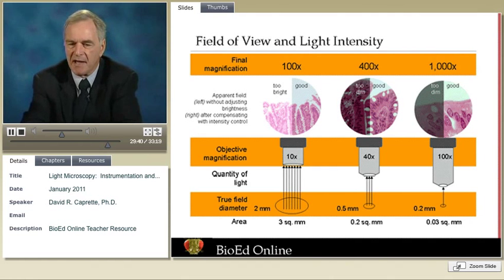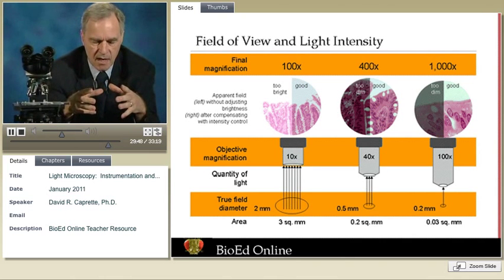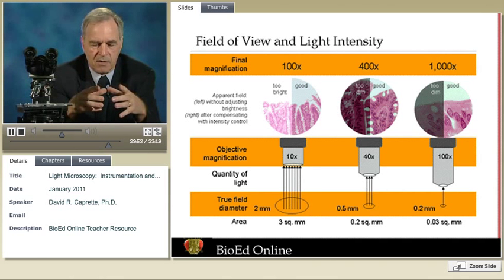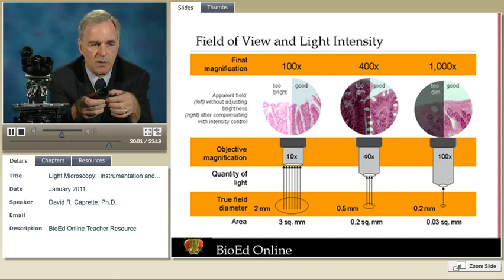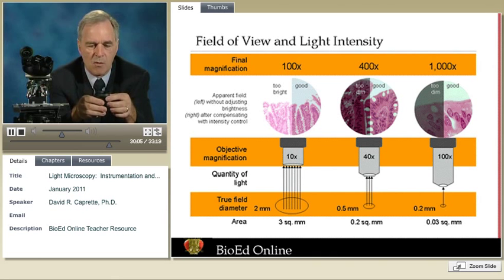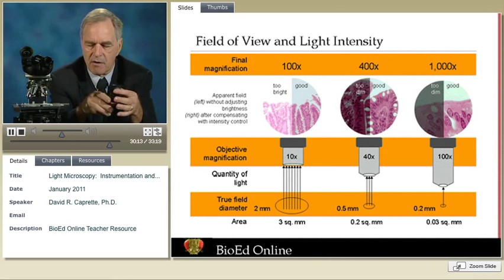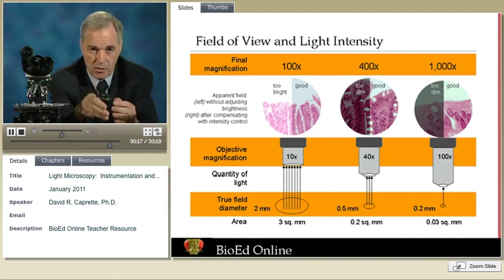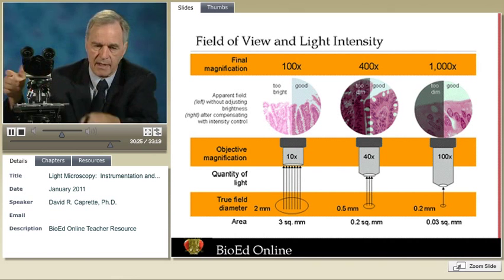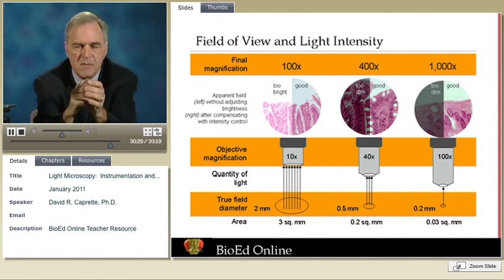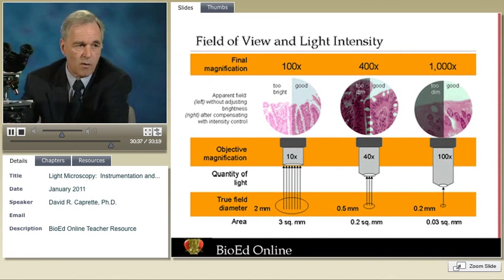When viewing at very low power, you're viewing a large area of specimen and the amount of light reaching your eye is also quite large. When you look through an eyepiece, you see the same apparent field of view regardless of magnification. At low power, light from a 5-millimeter-wide area diameter is coming up to your eye — quite a lot. When you work up to a 40-power objective, you're looking at a much smaller area, and a couple of orders of magnitude less light reaches your eye, so you'll need to brighten the illuminator quite a bit.